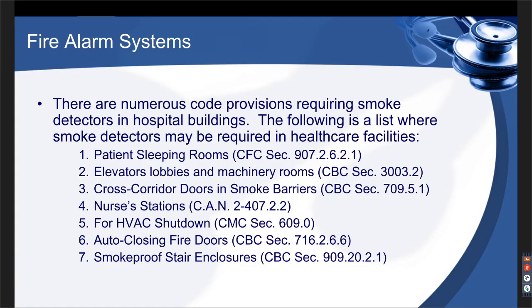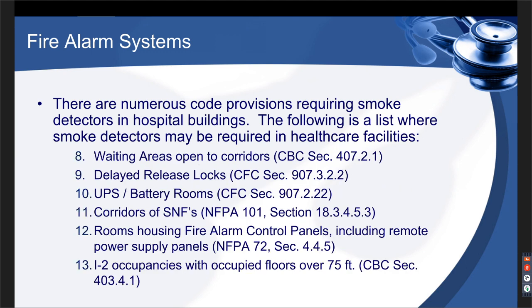However, there are numerous other provisions of the code that might require smoke detection elsewhere. And so here's a few of them. If you have elevators, obviously you need smoke detectors in the elevator lobbies. If you are required to have air handlers shut down, you may need smoke detectors, automatic closing doors, etc. So these are just 13 examples of other locations in the code that require smoke detection in addition to the requirements of 907.